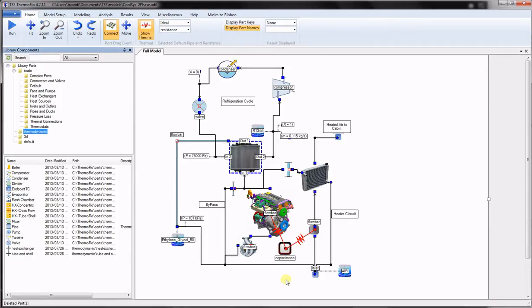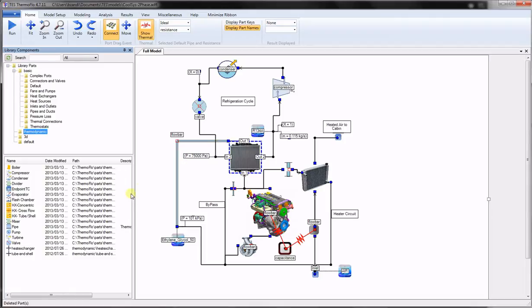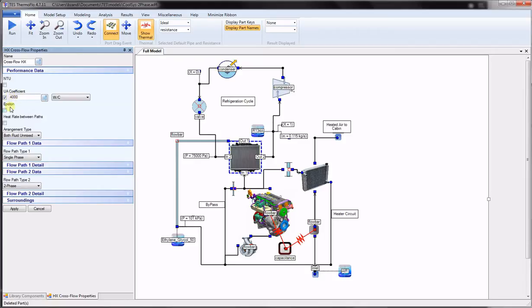Heat exchanger components give the user the capability to transfer heat from a thermodynamics flow path to another flow path which can be standard or thermodynamics. In this model, a cross-flow heat exchanger is used to transfer heat from the engine coolant to a refrigeration system. These heat exchanger components are based on Kays and London's heat exchanger approach. The user may provide or solve for any of the heat exchanger parameters in the properties menu. These include the NTU or number of transfer units, the UA coefficient which is the overall conductance between the two flow paths, the exchanger effectiveness, and the heat rate. Then the user chooses the arrangement type from the pull-down list box.